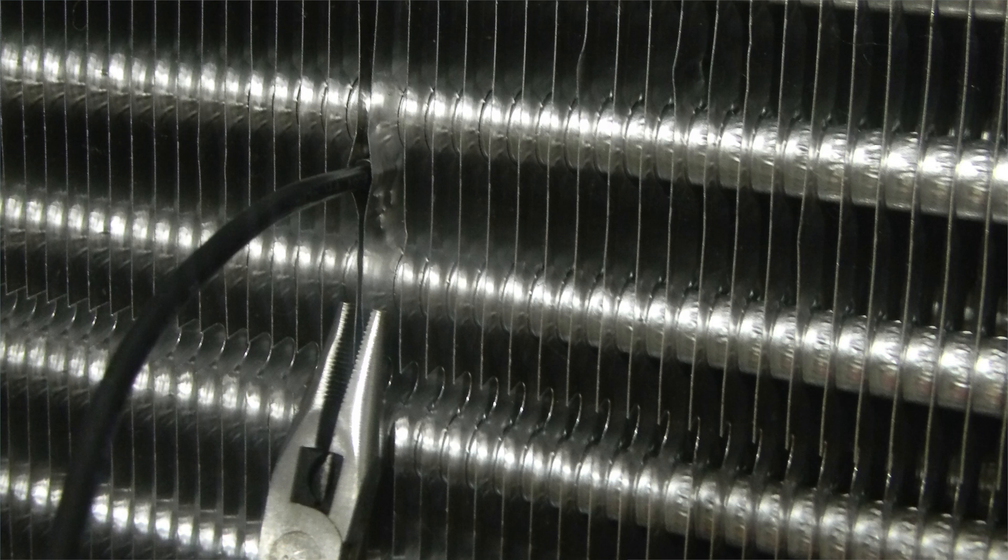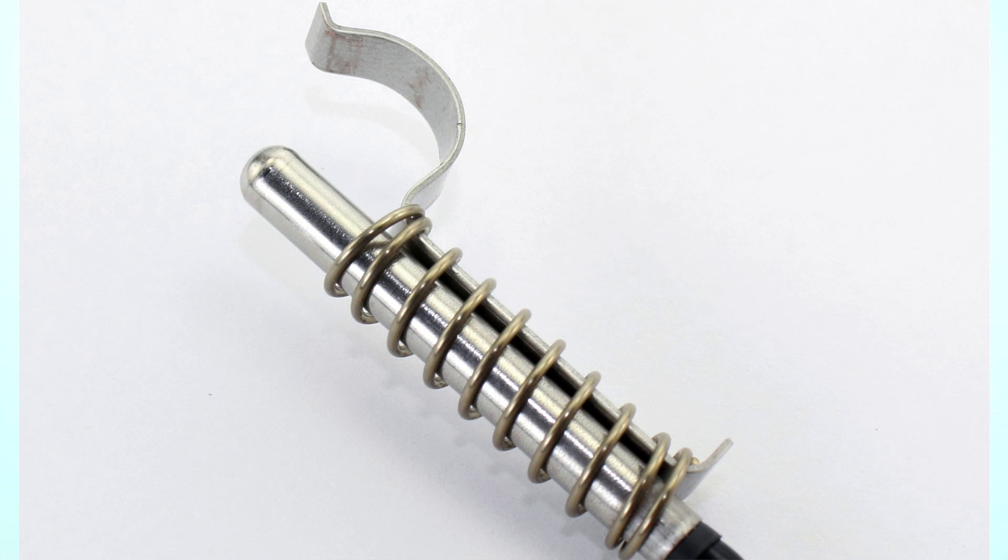When installing the sensor on an evaporator with 4 to 6 fins per inch, the fins themselves should be sufficient to hold the sensor in place. On installations with wider fin spacing, a coil sensor clip should be used. There are two methods that can be used to install the sensor.